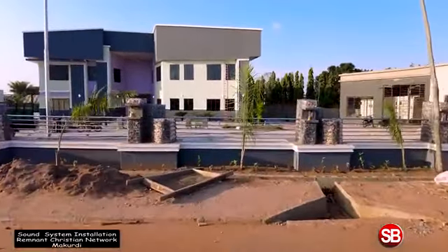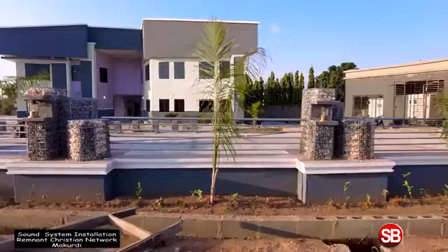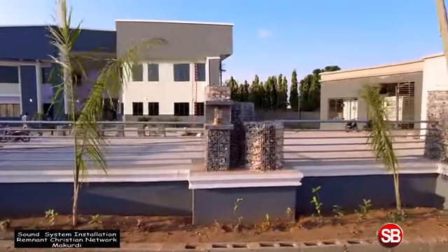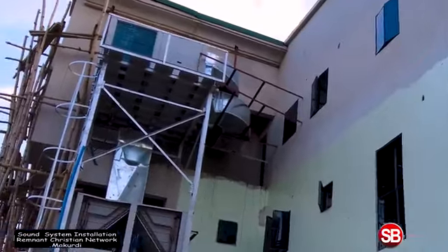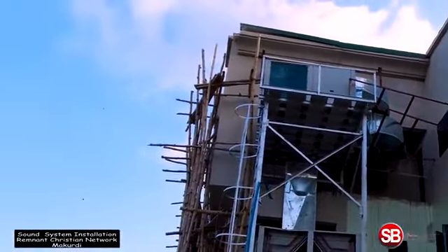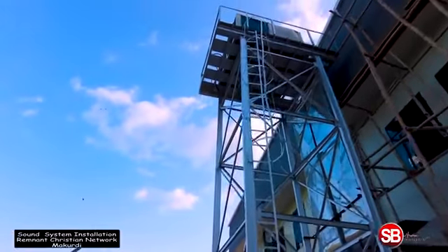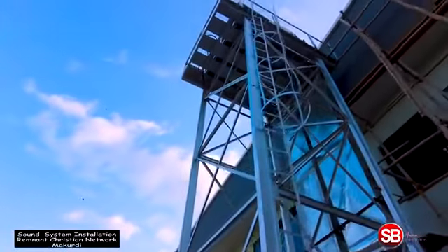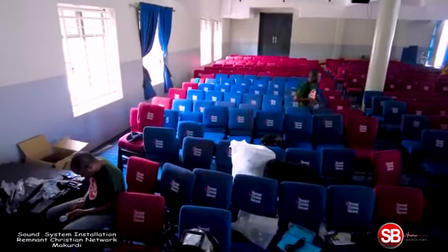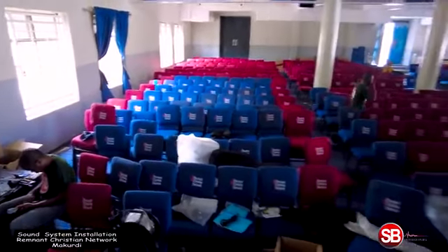We insisted the generator will need to be loaded with the air conditioners, light, etc. before the sound is turned on. The generator could not be loaded and we could not have power on the sound system for almost 3 days until an alternative was made that only lasted for a couple of hours.